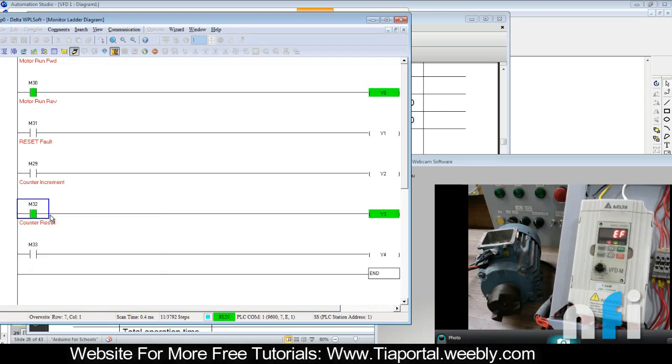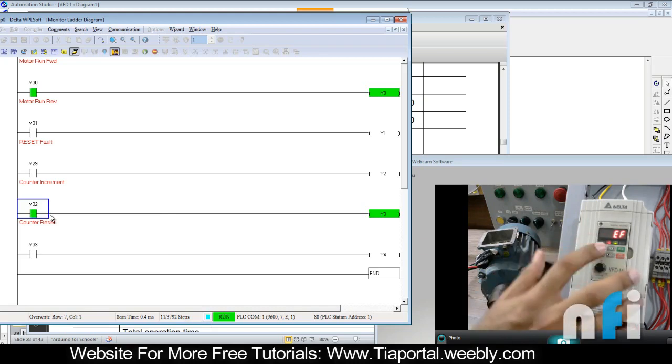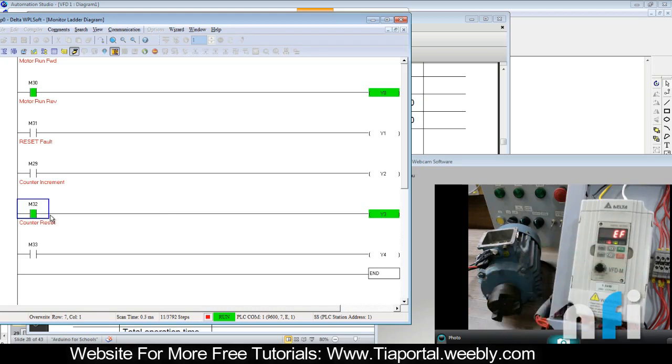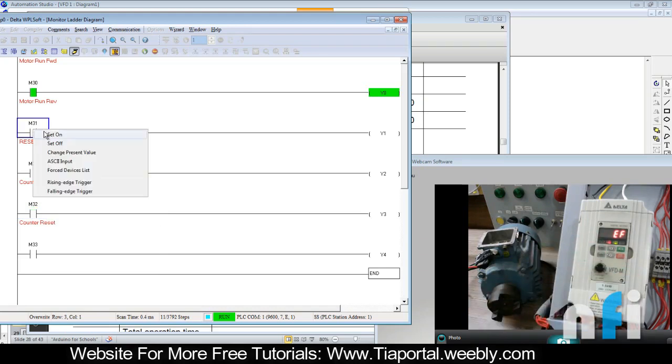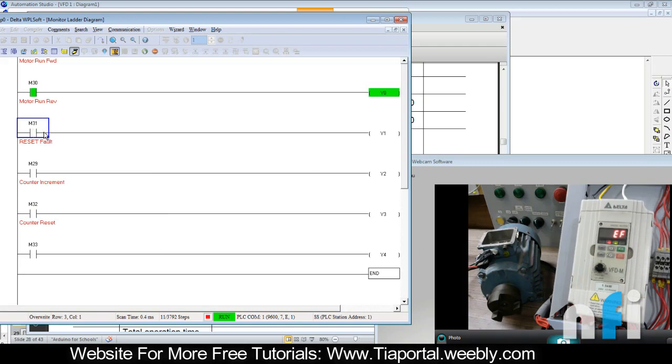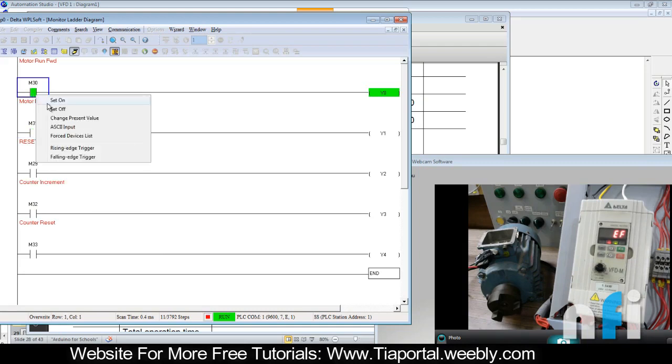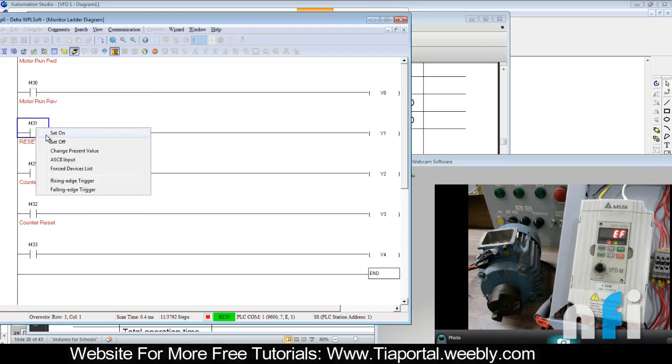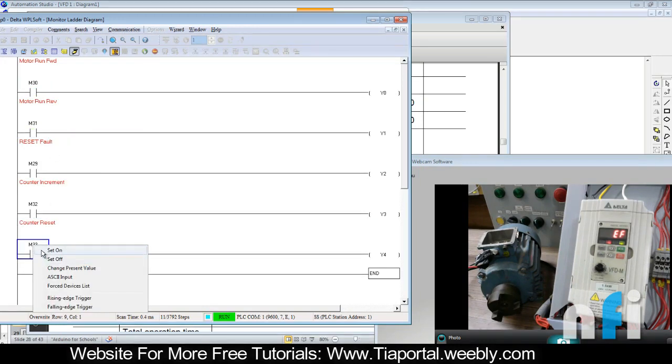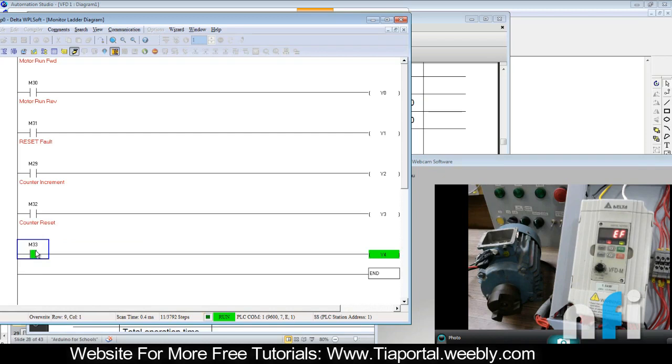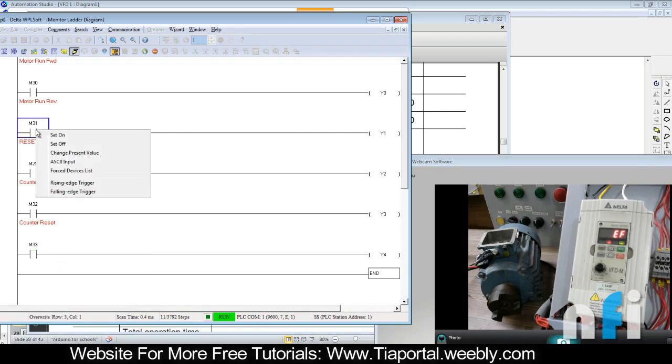And beyond that you'll have a fault. This is EF. To remove that fault, we have to do reset. But in that case, the motor should be off. Now one more thing: you have to reset the counter as well, otherwise the fault will not go.